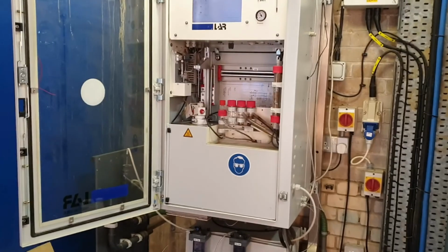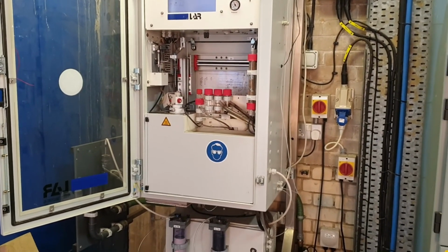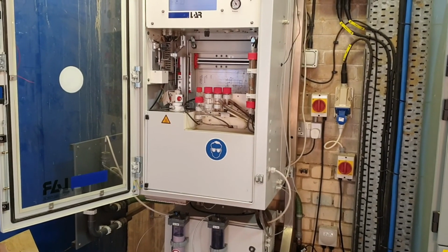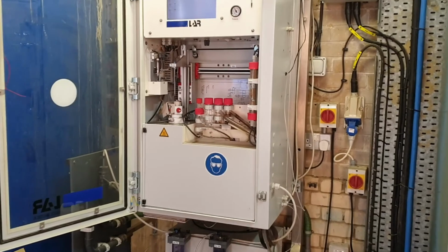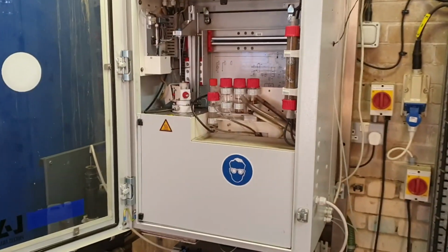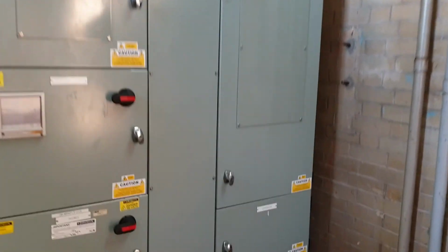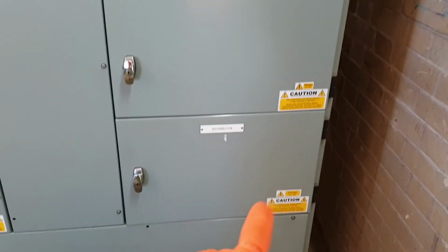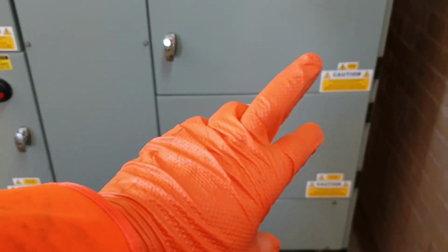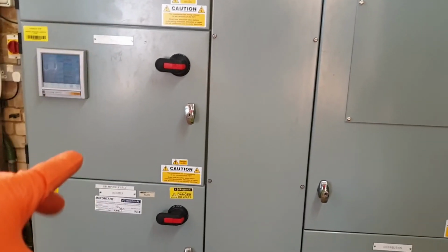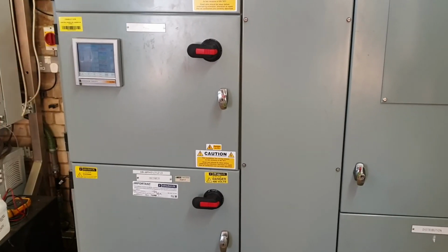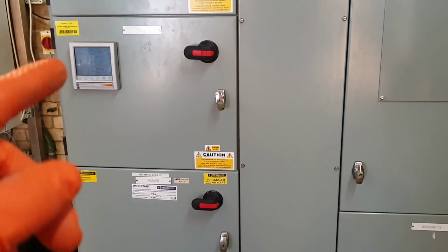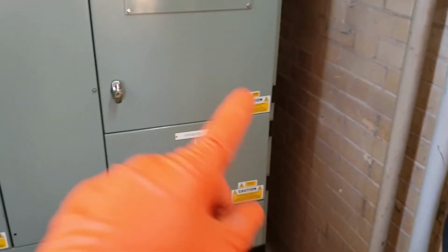This system is controlling how they treat the water that comes off the runway at the airport. Sorry, this is at an airport. When I got here, the sample pump is outside. The machine was reading 0 and wasn't getting any sample. Now they've put a new panel design in, and included in that panel there's a breaker that goes to the sample pump, but there's also a sample pump controller which takes a signal from the PLC system, which is in one of these other boxes. The PLC system sees whether we've got water coming in from the flow meter, and if we have, it should let the sample pump run, but it wasn't.